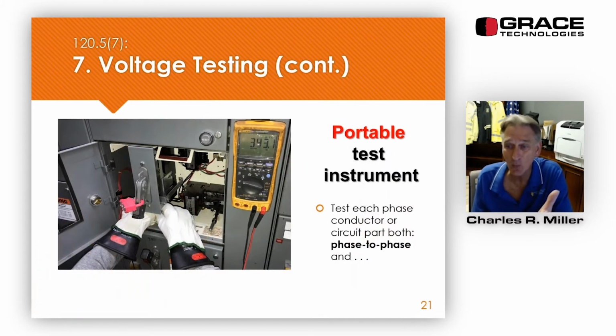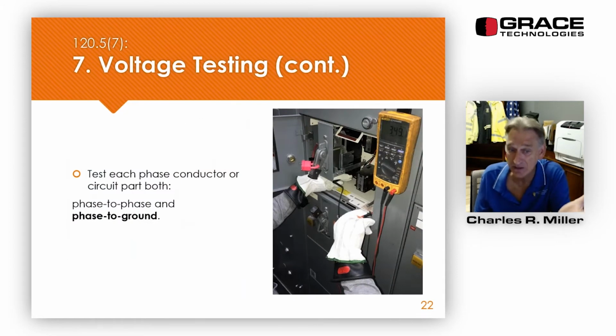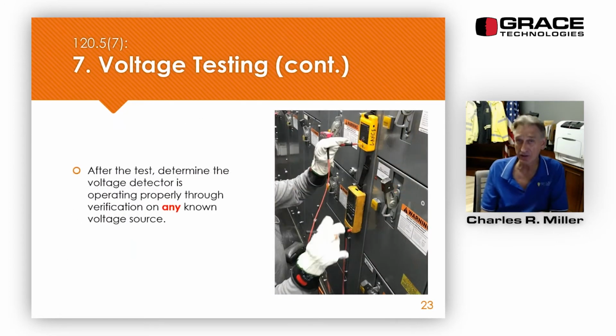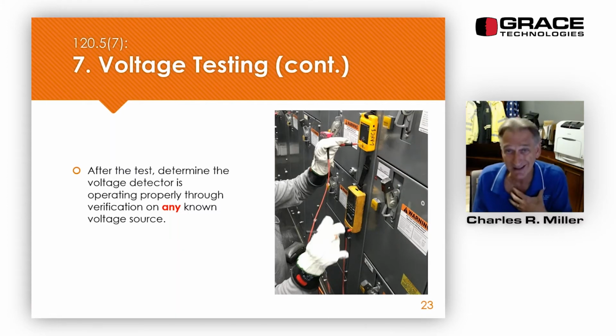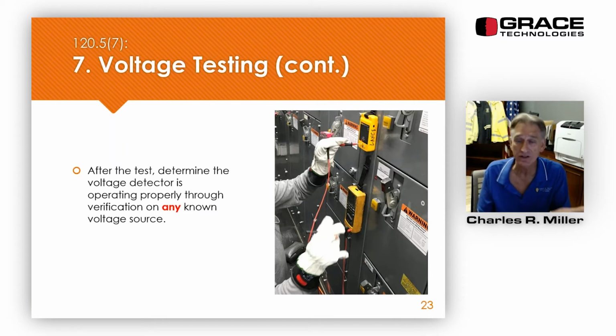All right, then we test each phase conductor or circuit part, phase to phase and phase to ground. Then after we test phase to phase and phase to ground, we have to test our meter, what we typically call voltage detectors. Test instrument is the correct name. And so we test our meter again to make sure it is working.